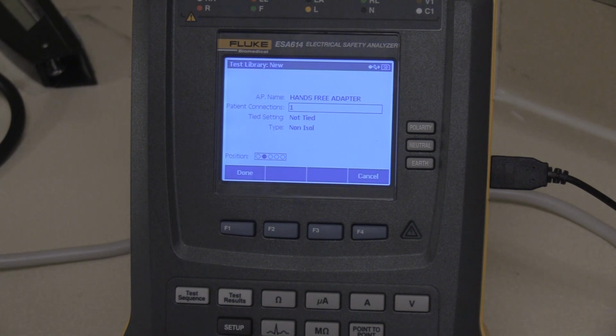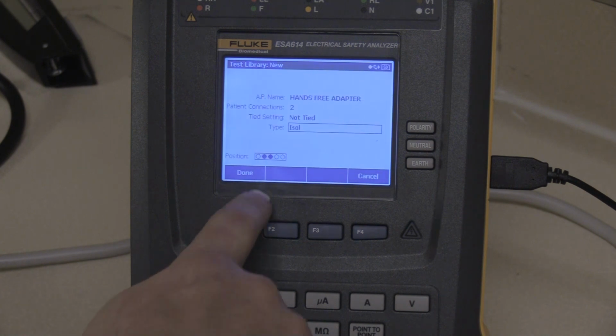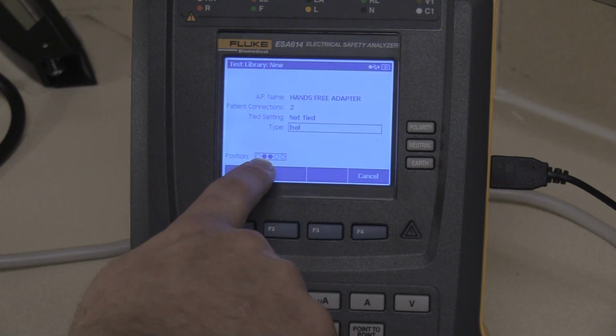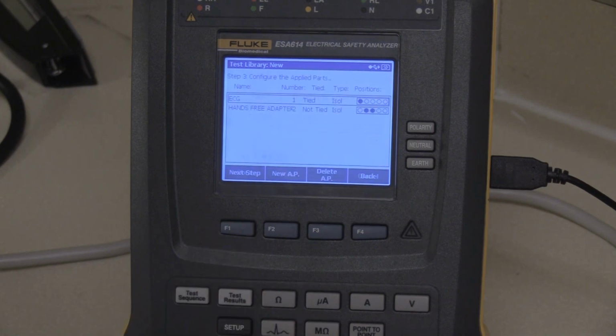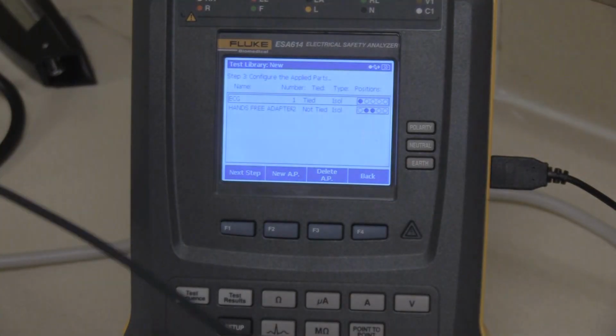And it's going to use 2 patient connectors. There's 2 wires on the hands-free adapter, so change this to 2. And they're not tied, they're independent. So that's correct, but they are isolated, it being a defibrillator. And then you can see the 2 ports that it's now assigned to. So we'll go ahead and hit OK. And again, just to review, there's our ECG on position 1.